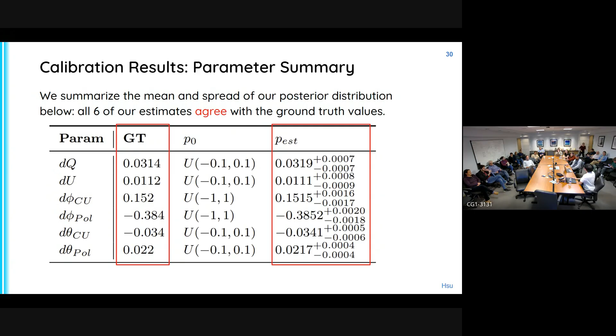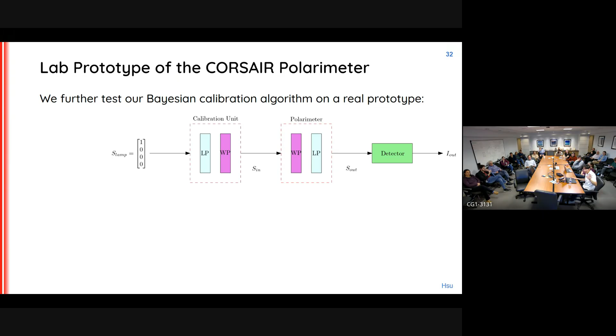Well, so we did a lab prototype for the CORSAIR polarimeter, and we're going to test this calibration algorithm on it. So this is the diagram of the whole pipeline, and I took some off-the-shelf Thorlabs optics and set up this whole pipeline. So you can see we have the lamp source in the front with the filter, calibration unit, polarimeter, and detector. Now, unfortunately, when I did this, we didn't have the actual CORSAIR detector, and we didn't have an infrared light source, so I just used visible light. But hopefully, in spirit, it captures most of what we're trying to test.